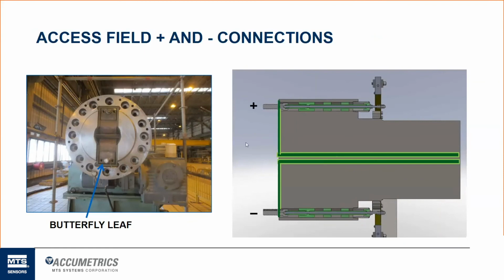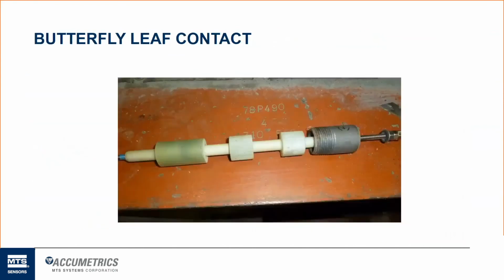So this one on the right is a cross-sectional view of how we make that connection. Inside that coupling flange bore is how they bolt together the two butterfly leaves that match up. We just drill and tap a 1/4-20 stainless steel threaded rod right into one of those large hex head bolts, and we run our threaded rod right through that coupling flange bore directly into our rotor mounted transmitter. So that would be your plus and your minus field voltage connection. It's a very reliable way of getting access to that electrical connection, and is as least invasive as possible for the end users. They really don't have to modify any part of their machine except for drilling and tapping the two bolts where that contact is made. So that's an example of the butterfly leaf field voltage contact.